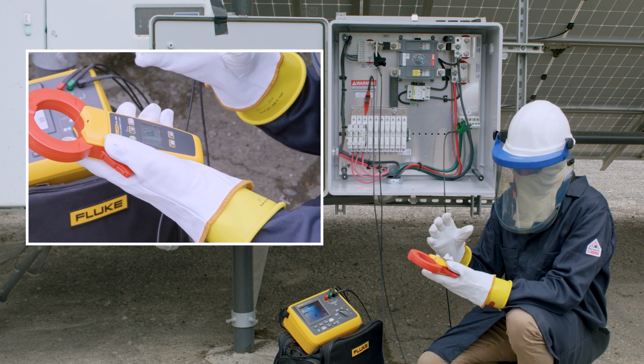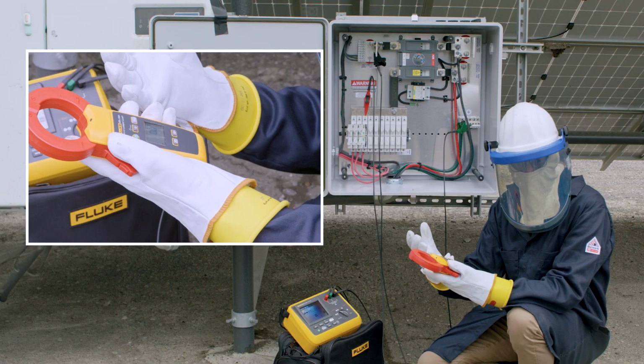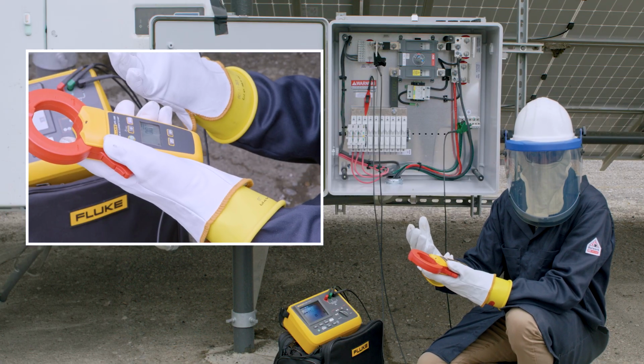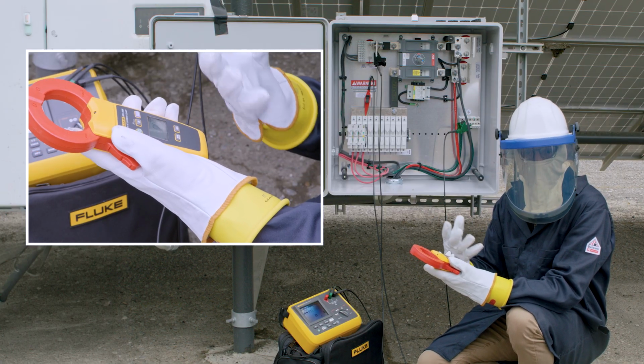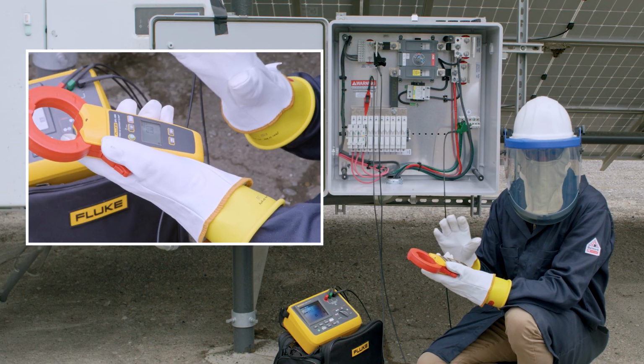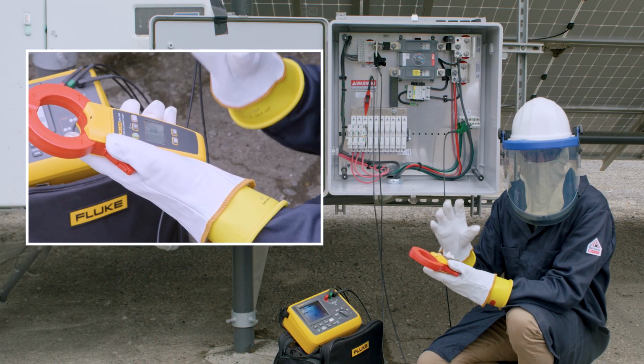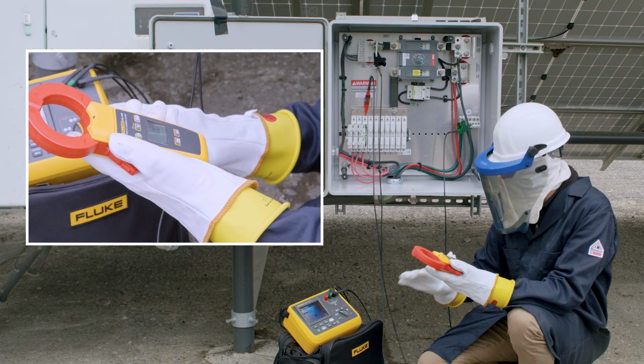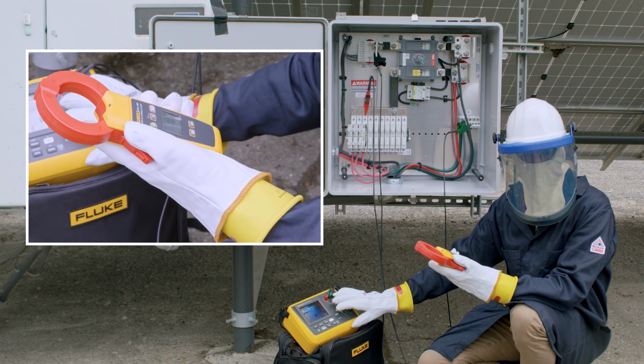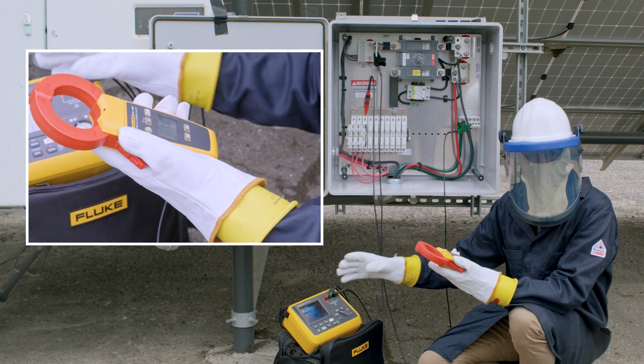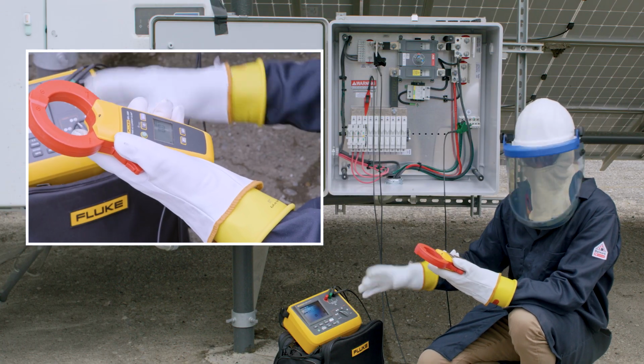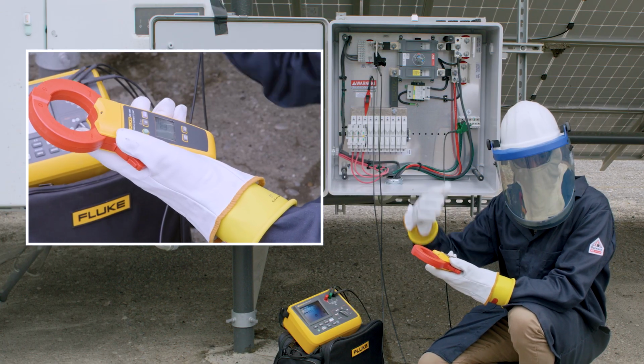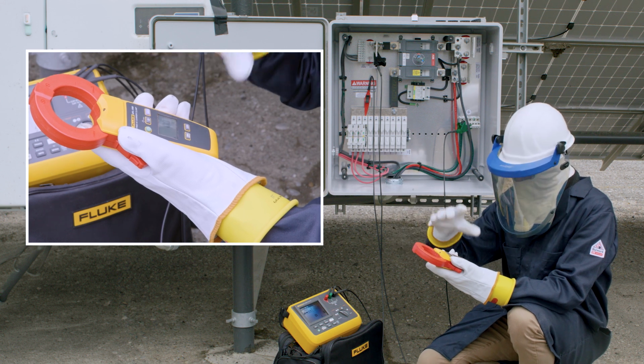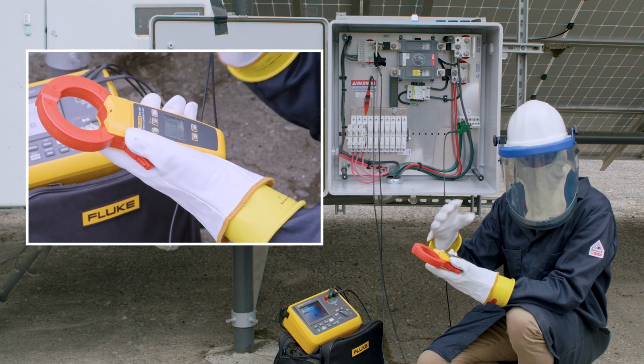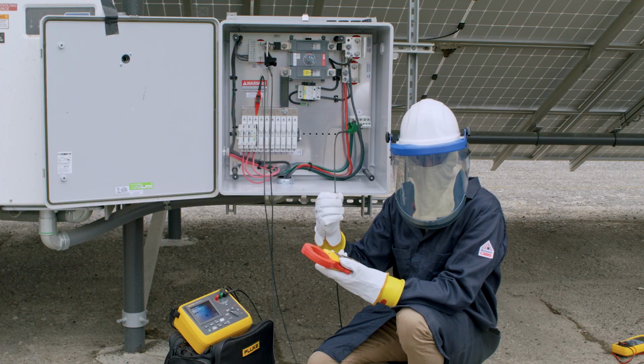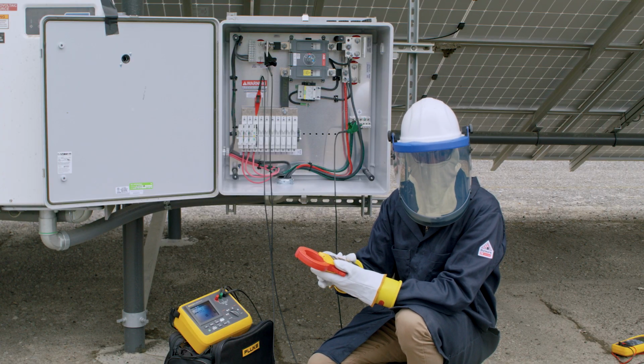So if you're having a problem where you know you have high capacitance in the system or suspect there's high capacitance in the system and you're seeing signal everywhere, use the clamp and switch that to the bandpass mode. Now, this only works if you're sending the signal from the transmitter in array mode. It will not work if you're sending in unit mode. So make sure that you have it set to array mode. It could be in either high or low, and then use the clamp, and that may allow you to locate the ground fault easier in systems with high capacitance.